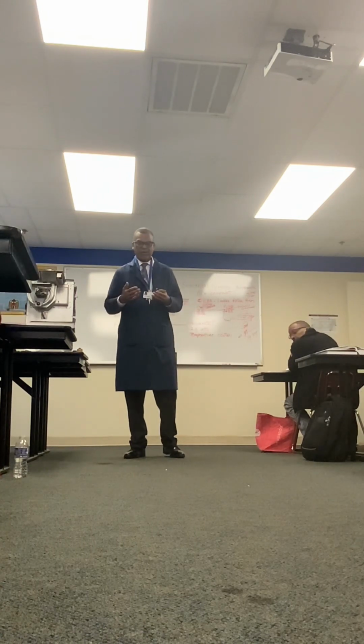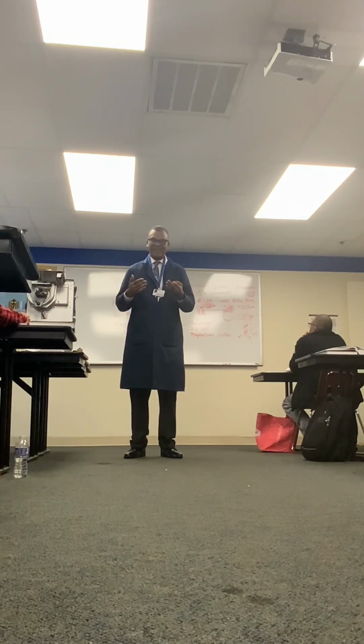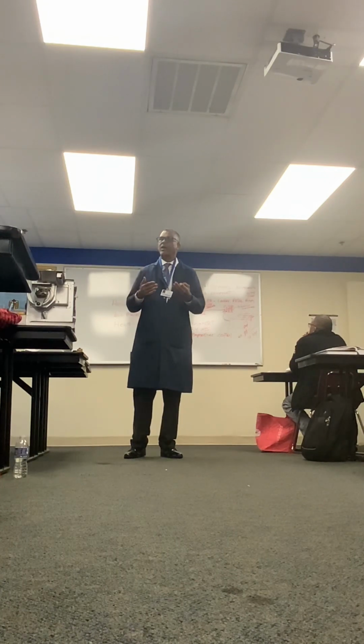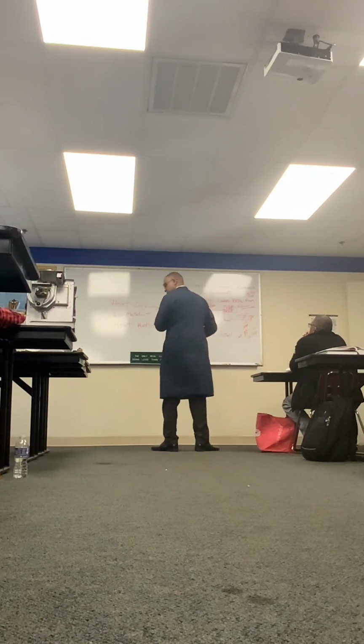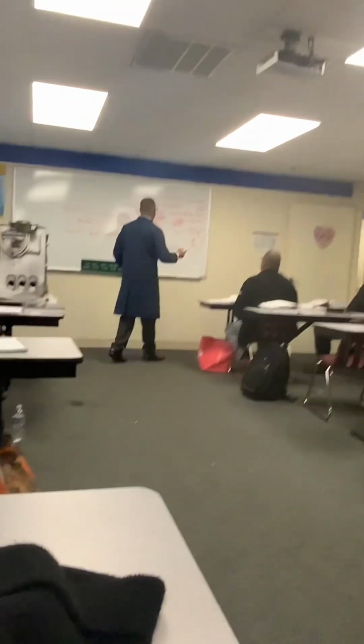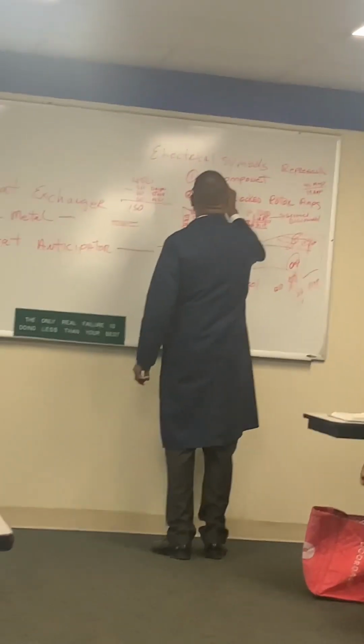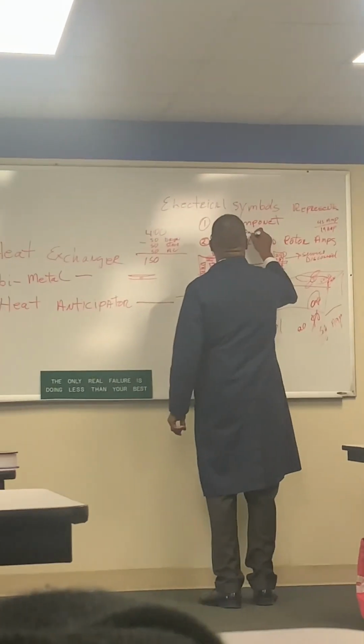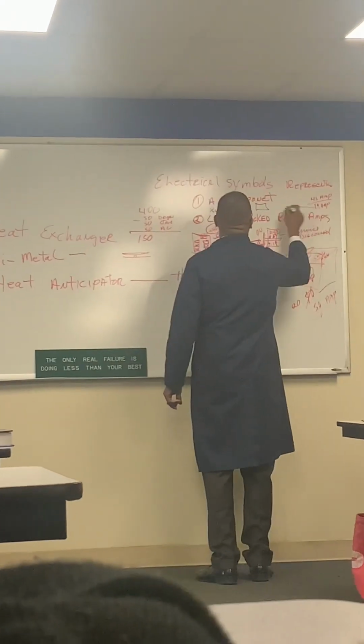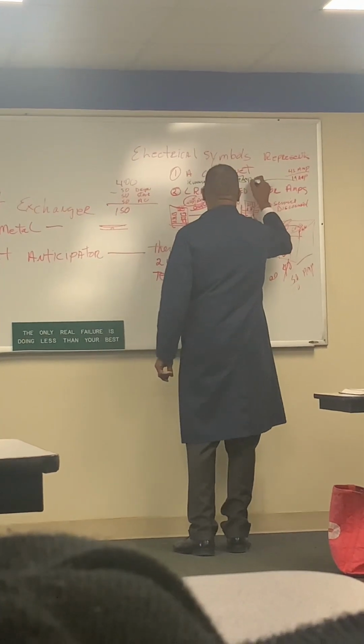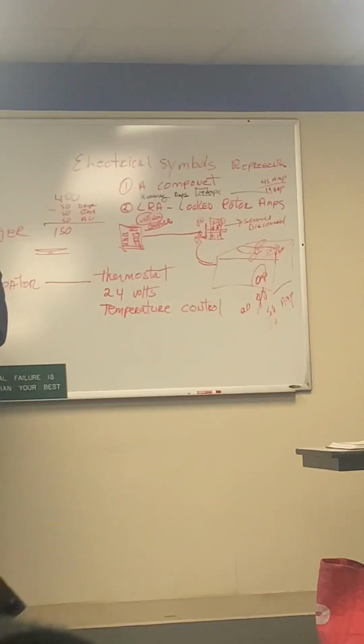as electrical, lock rotor is when we exceed the nameplate data of that motor, which would be RA, running amps. Guess I should have said that. How many above? That's what I'm trying to see. How much above? Okay, so it's called running amps. Running amps would be that 19 amps, okay? Lock rotor would be probably anything over 20 amps. It's starting to pull on the safety.